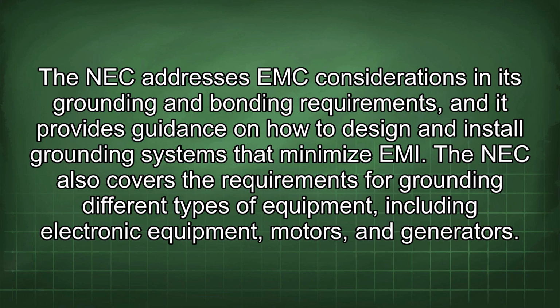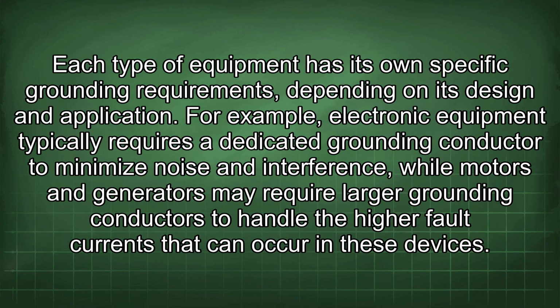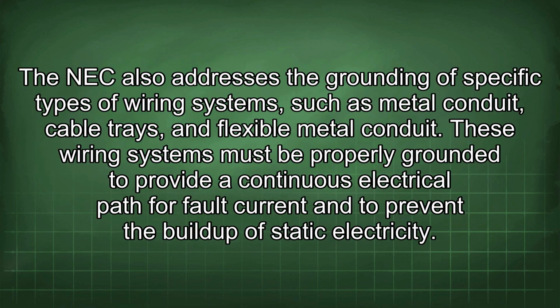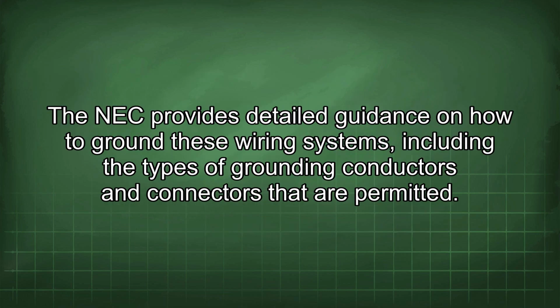The NEC also covers the requirements for grounding different types of equipment, including electronic equipment, motors, and generators. Each type of equipment has its own specific grounding requirements, depending on its design and application. For example, electronic equipment typically requires a dedicated grounding conductor to minimize noise and interference, while motors and generators may require larger grounding conductors to handle the higher fault currents that can occur in these devices. The NEC also addresses the grounding of specific types of wiring systems, such as metal conduit, cable trays, and flexible metal conduit. These wiring systems must be properly grounded to provide a continuous electrical path for fault current and to prevent the buildup of static electricity. The NEC provides detailed guidance on how to ground these wiring systems, including the types of grounding conductors and connectors that are permitted.